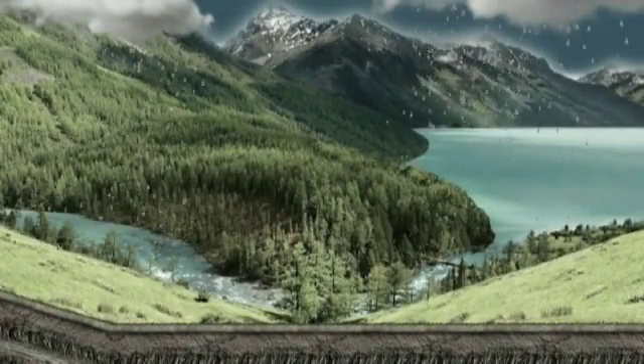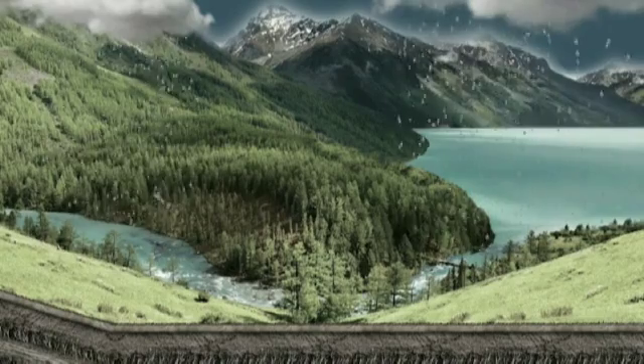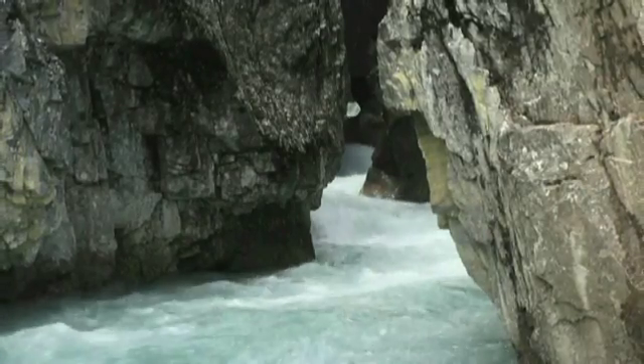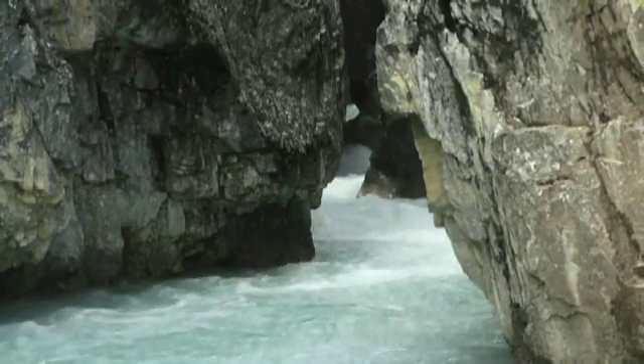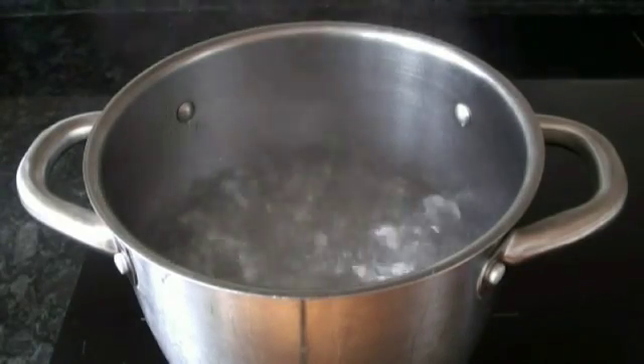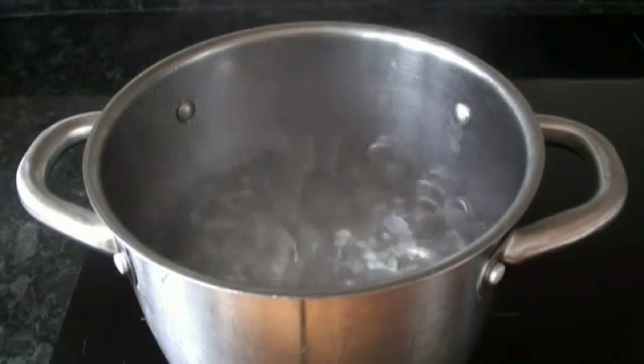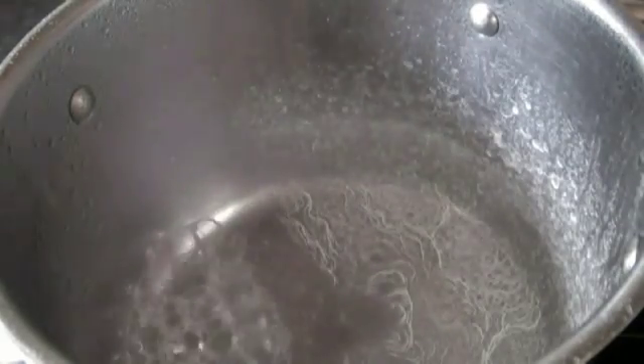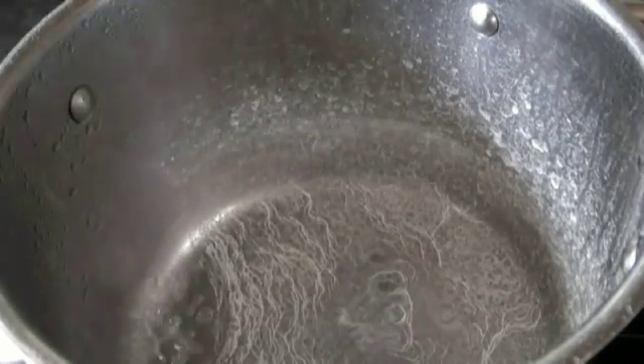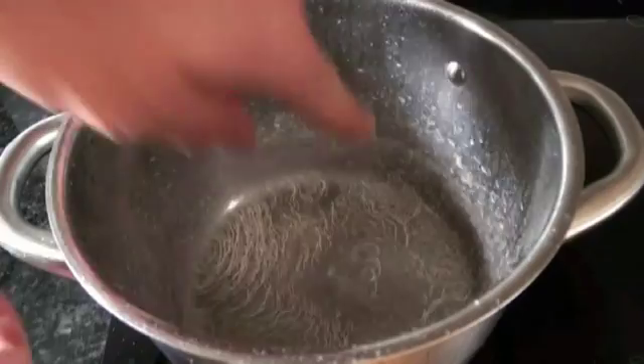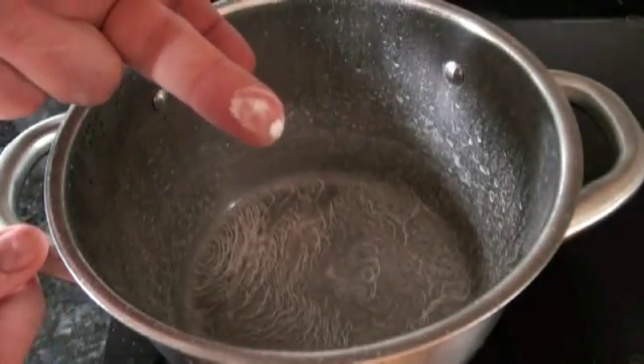As rain falls, it absorbs CO2 from the atmosphere to create carbonic acid. When it comes into contact with limestone or chalk, it causes particles to dissolve, creating calcium bicarbonate and forming hard water. The calcium bicarbonate remains dissolved until the water is heated, whereupon it releases the carbon dioxide, reverting the calcium back to its carbonate state by precipitating hard, ionically charged crystals, which become attracted to the closest surface exhibiting an opposite ionic charge, typically the pipe wall or heater element. In this way, the crystals form together to produce scale deposits.